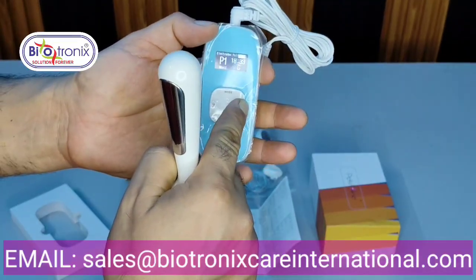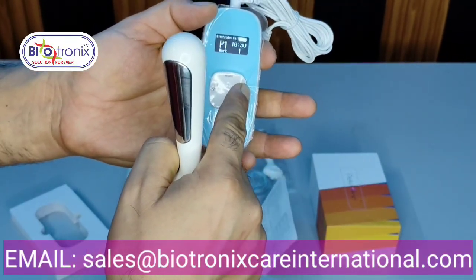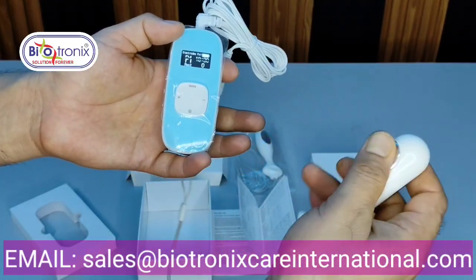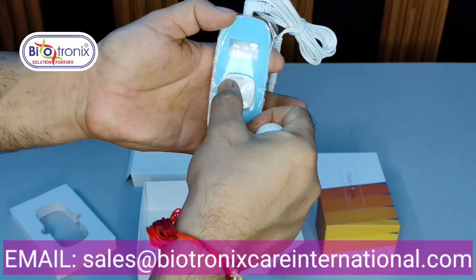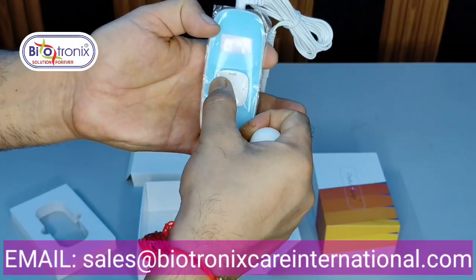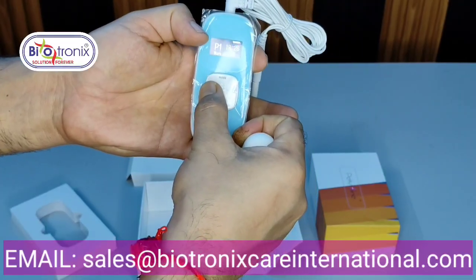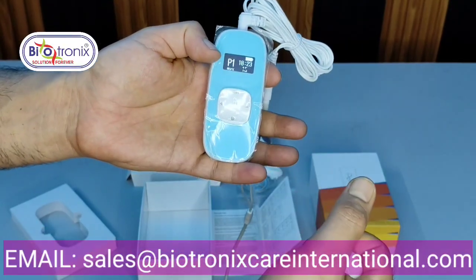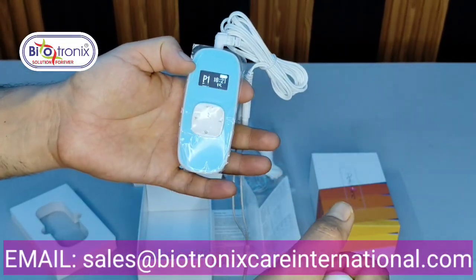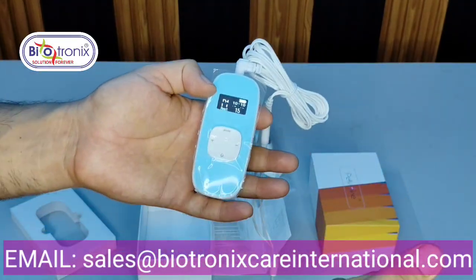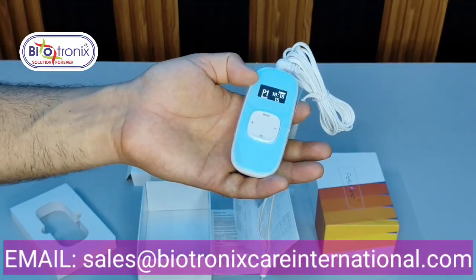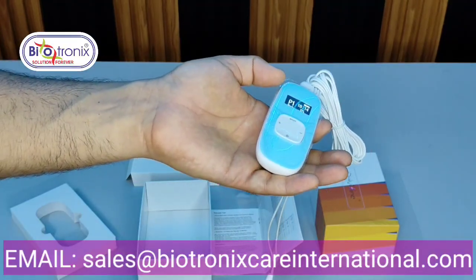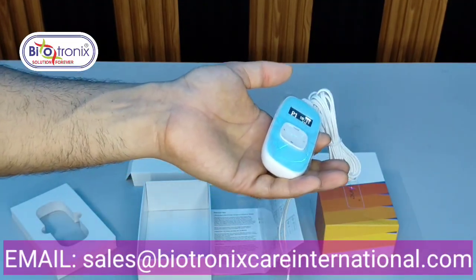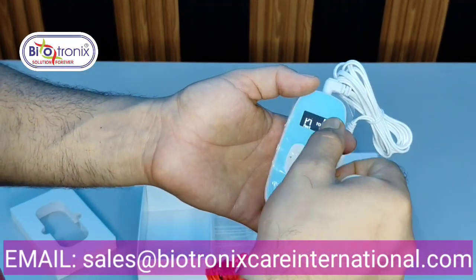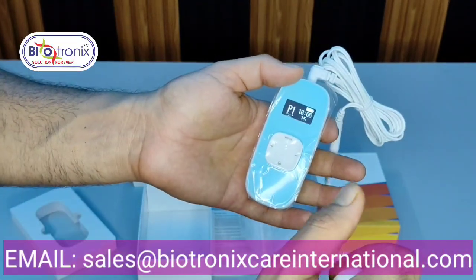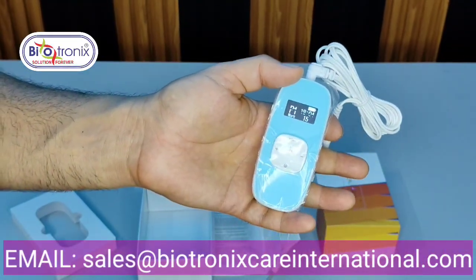So now I will decrease the intensity to 0 and reinsert the probe. Reinsert the probe like this, and now I increase the intensity. So electrode fault will disappear. This is to prevent electric shock and so on, and it indicates whether the probe is in contact or not. If the probe is not in contact, there is no use of your device. So the device will indicate that the probe is not in contact, and you need to reinsert it.